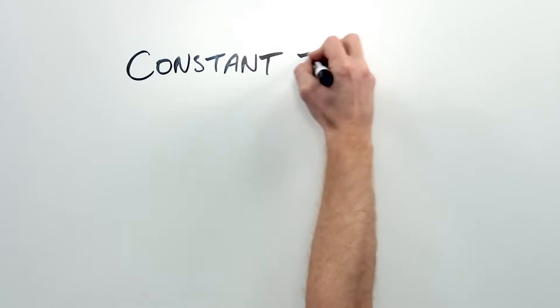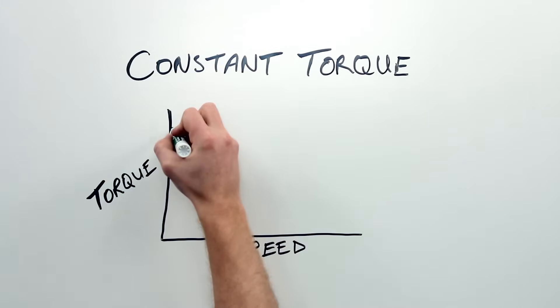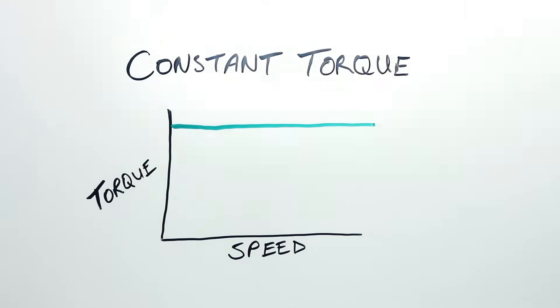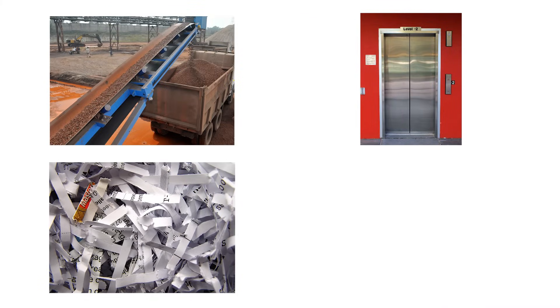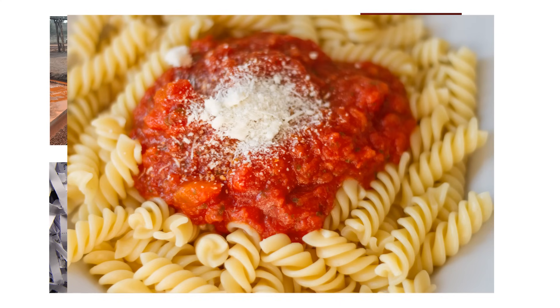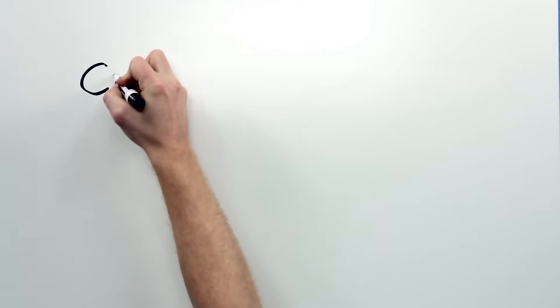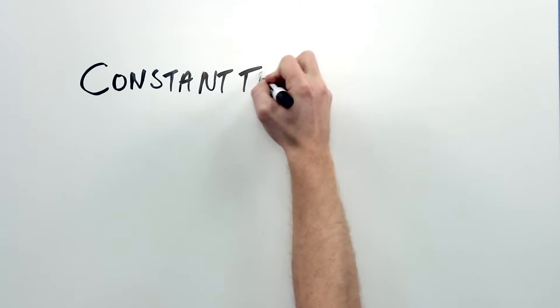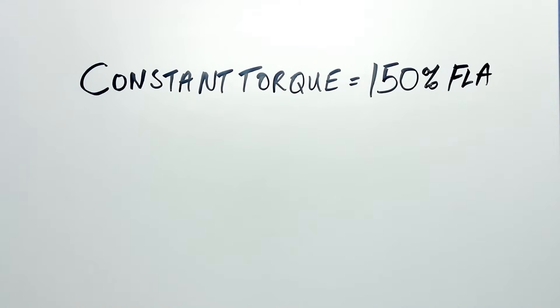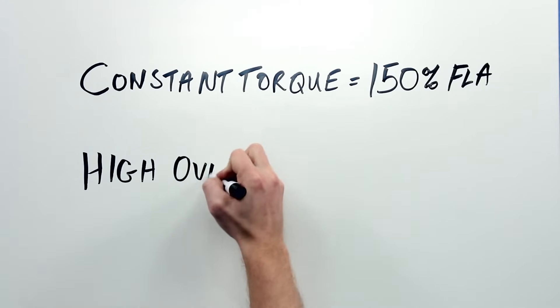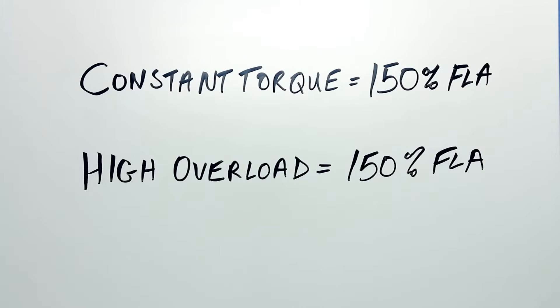If the load is not variable torque, it's likely what's called a constant torque load. Constant torque loads require the same amount of force to move the load at slow speeds as it does at higher speeds. Examples of constant torque loads are conveyors, elevators, shredders, or extruders that extrude the pasta that you buy at the grocery store — basically any load that isn't a fan, pump, blower, or compressor. Since constant torque loads can change frequently, like more boxes being added to a conveyor belt, the drive must be able to handle brief periods of extra current drawn by the motor. So we size it at 150% of the motor's FLA for constant torque loads. We call this a drive with high overload capability.